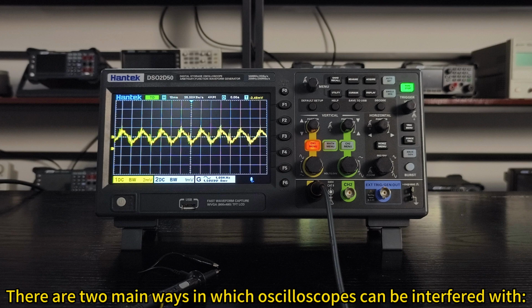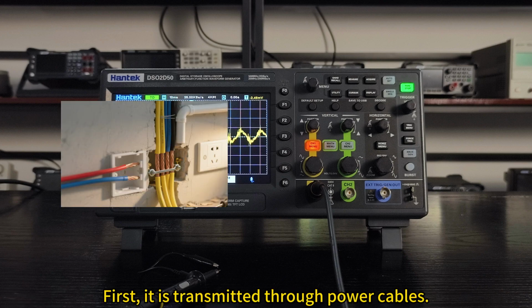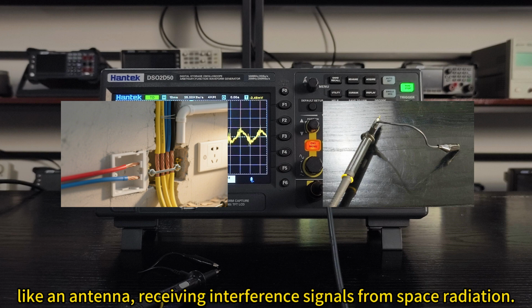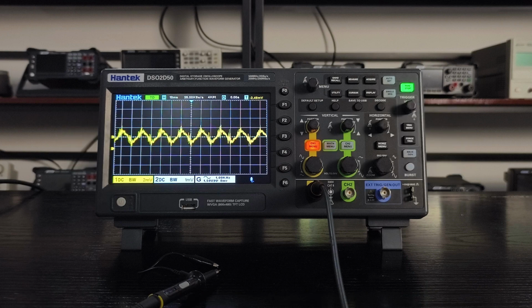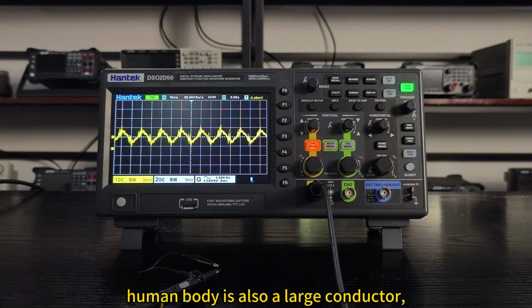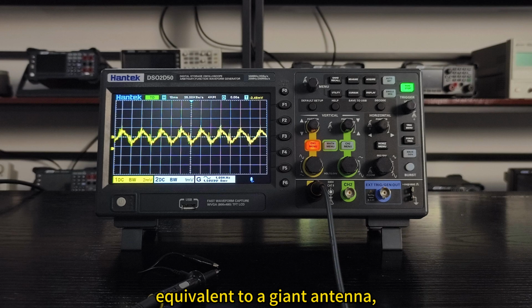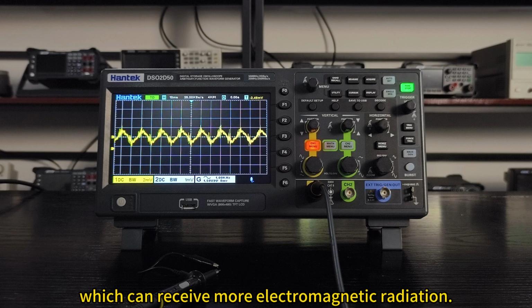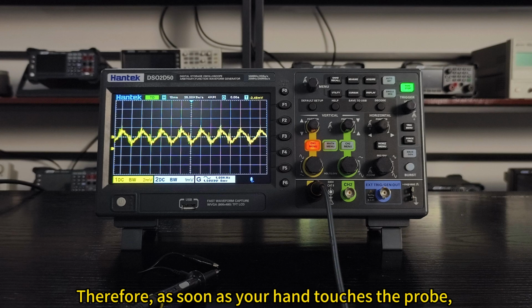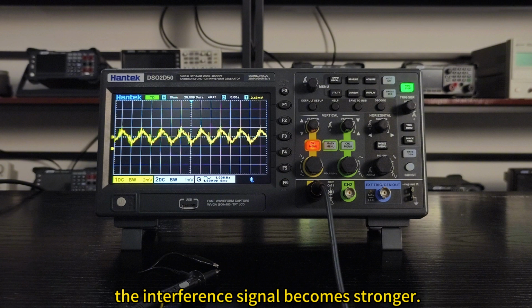There are two main ways in which oscilloscopes can be interfered with. First, it is transmitted through power cables. Second, as is the case now, the probe is exposed to the air like an antenna, receiving interference signals from space radiation. What's more interesting is that the human body is also a large conductor, equivalent to a giant antenna, which can receive more electromagnetic radiation. Therefore, as soon as your hand touches the probe, the interference signal becomes stronger.